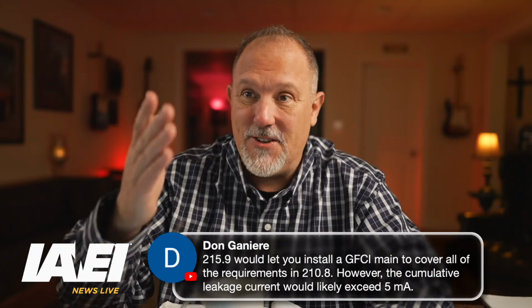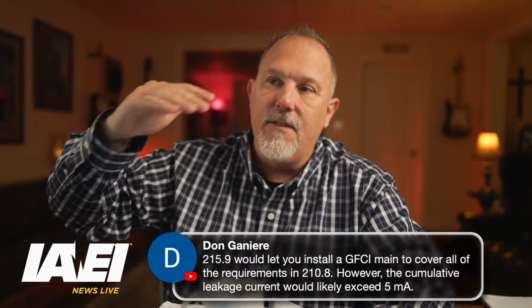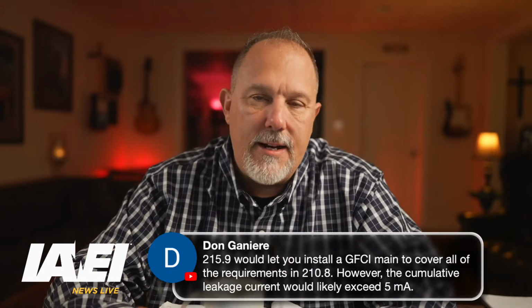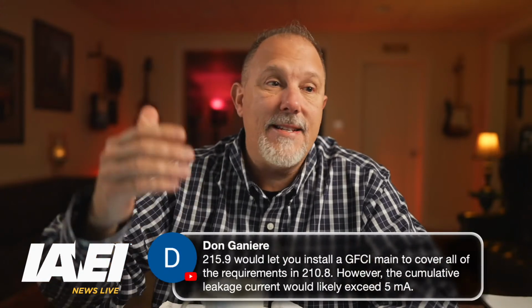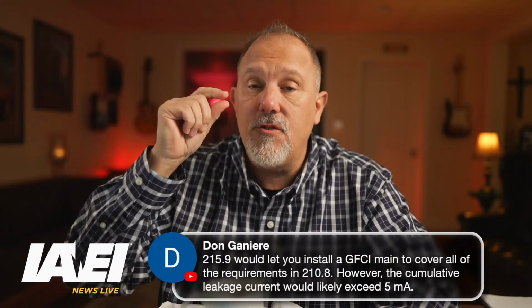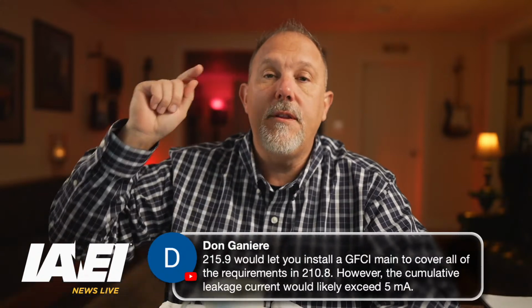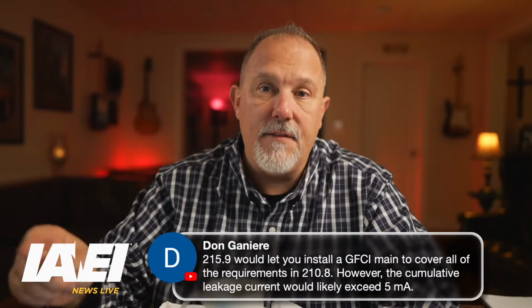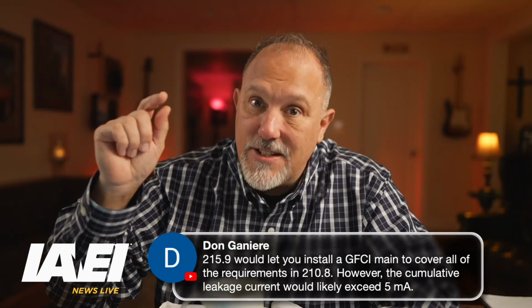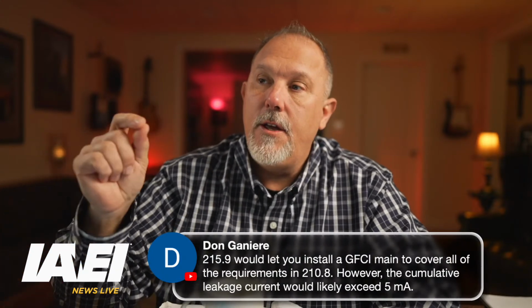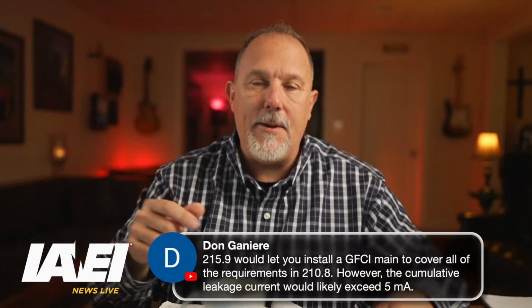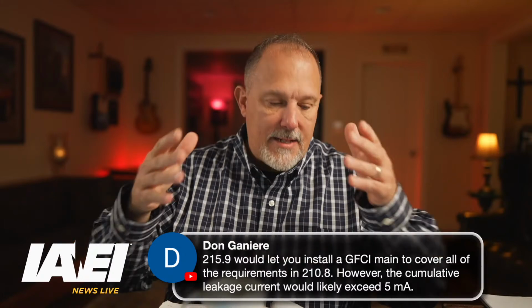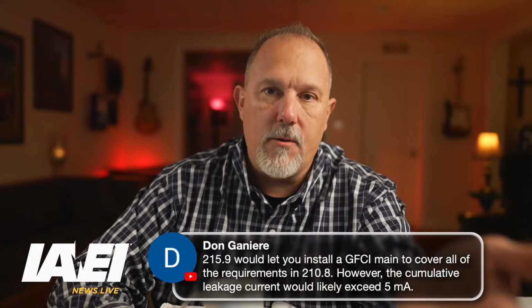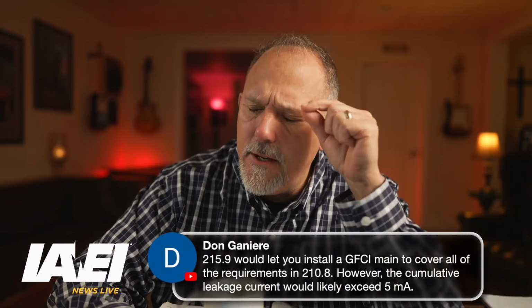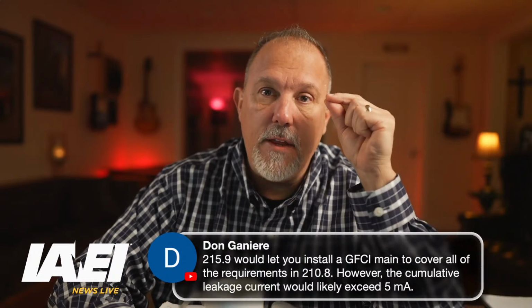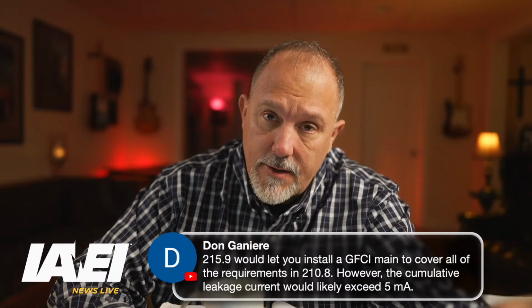Absolutely. Now, Don, this is the challenge with putting any level of ground fault protection up there at the main. I know we have 230.95 that is a GFPE requirement, but it presents the same challenges. If you're trying to solve a problem in a branch circuit, you put the GFCI or GFPE at the beginning of that branch circuit, or as close to where your problem is. The reason is that when that goes out, you're limiting the outage in the system. You might say that gives better reliability. Well, it would, but it's even more important to make life easier for the individual who has to re-energize the circuit.